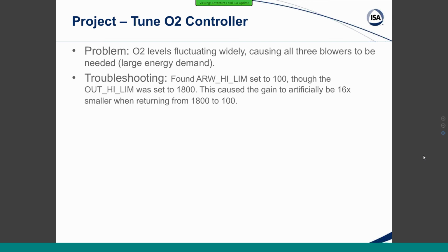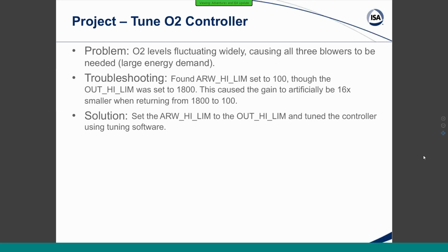All three were needed, but they were turning on, turning off, and basically cycling pretty badly with a large energy demand. When we looked into it, we found, again, that this was tied to that anti-reset windup. The ARW high limit was set to 100, but the output high limit on the blower was actually set to 1800. So for 1700 of the 1800 of this range, going in one direction from that output high limit down to the ARW high limit, we had a gain that was 16 times smaller than when going in the other direction. So that was just wreaking havoc.